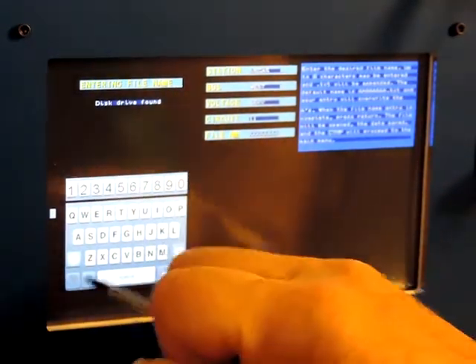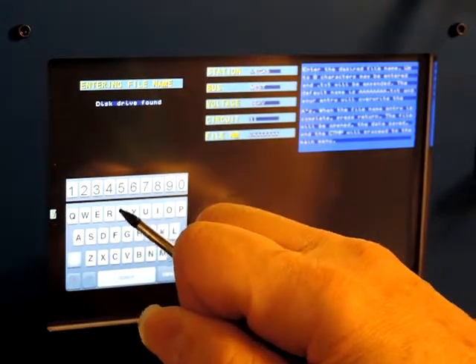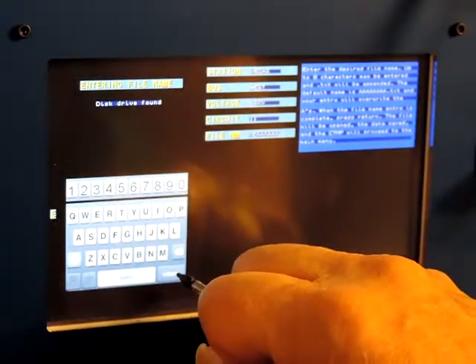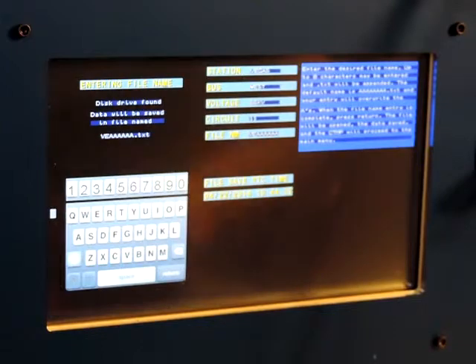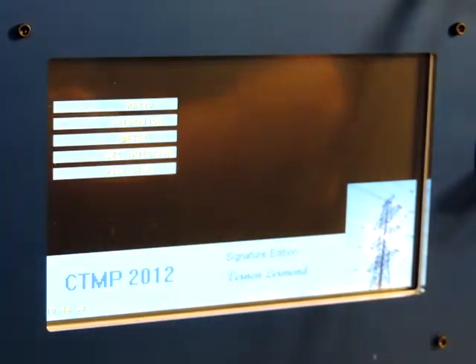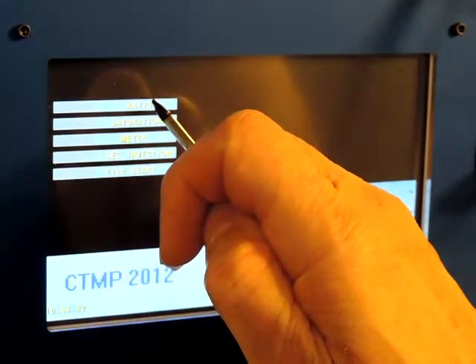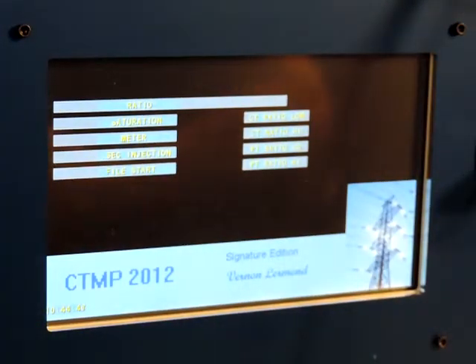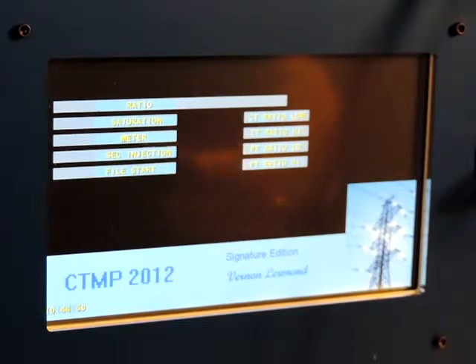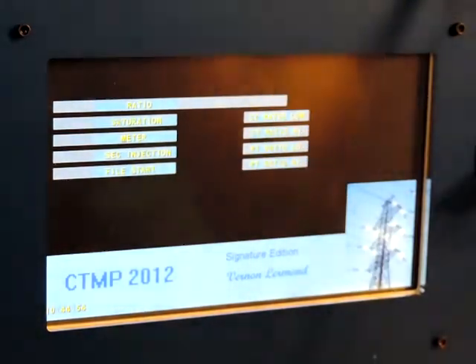Last is the file name — we'll call it 'VE' with the rest as A's, then press Return. Now let's open the file, which returns you to the main menu. The first test we're going to perform is a ratio test. Typically on one file you can do a complete set of CTs — A, B, and C phase. One file is the same as one data sheet and can hold three CTs or more if you wanted.